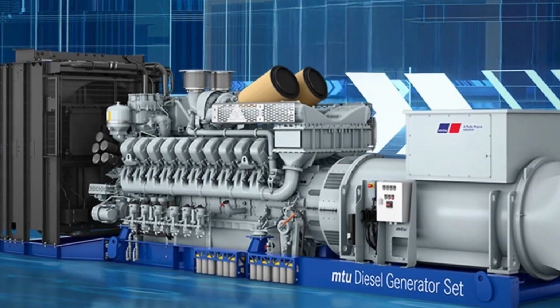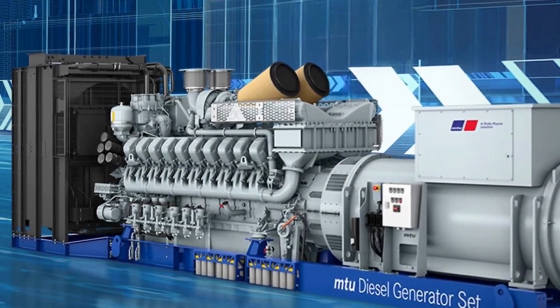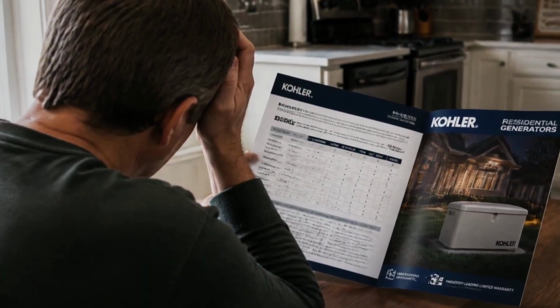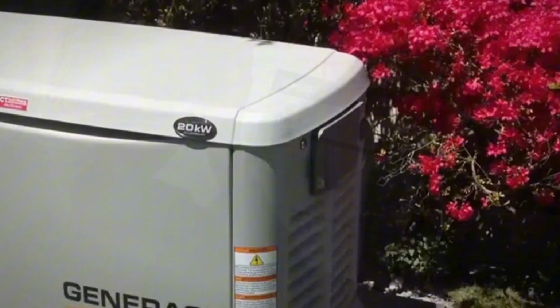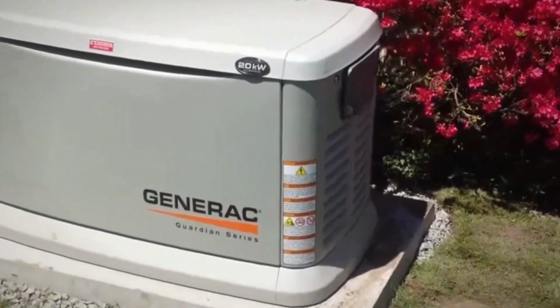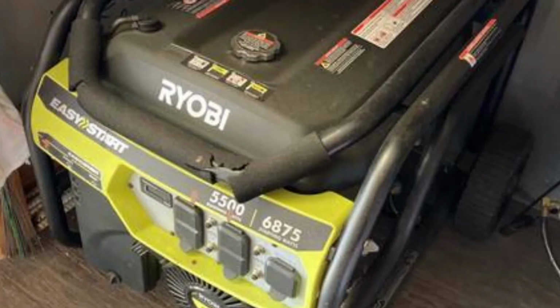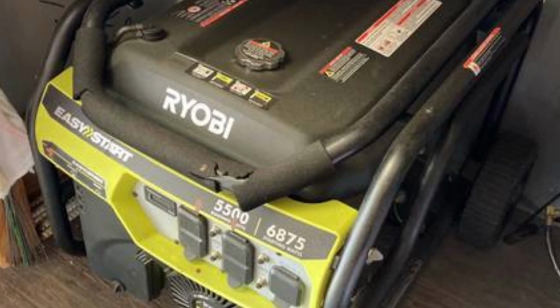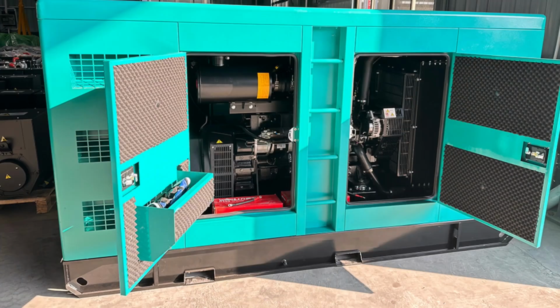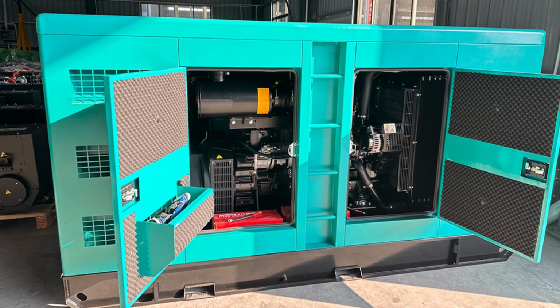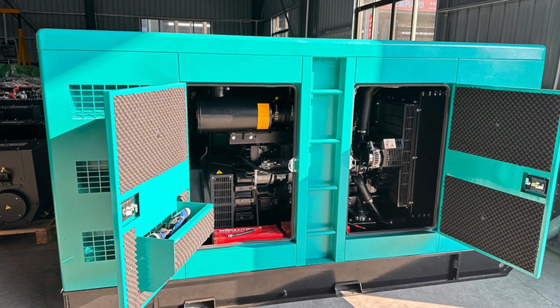If the generator or transfer switch can't smoothly manage those startup loads, voltage can dip, frequency can fluctuate, and the controller may trigger protective shutdowns or fault codes. Ironically, the generator itself might still be mechanically capable of running, but the electrical system protecting it decides something isn't right and shuts everything down.